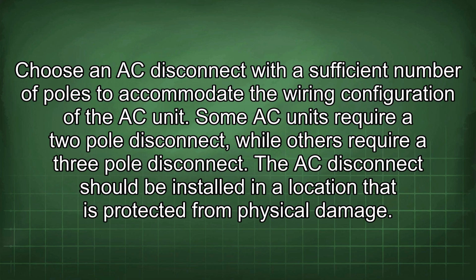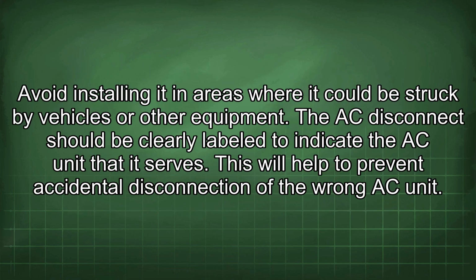The AC disconnect should be installed in a location that is protected from physical damage. Avoid installing it in areas where it could be struck by vehicles or other equipment. The AC disconnect should be clearly labeled to indicate the AC unit that it serves. This will help to prevent accidental disconnection of the wrong AC unit.